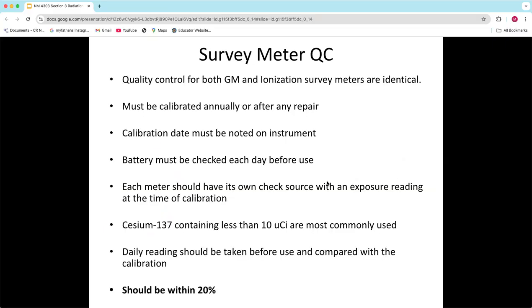All right. So when you talk about quality control, these are always test questions with quality control, whether it be cameras or meters or whatever. So both the GM and the ionization survey meters are pretty much identical on the quality assurance. They have to be calibrated annually, and I would add in the scintillation detectors as well. All of these require the same thing, but they have to be calibrated annually or after any repair.